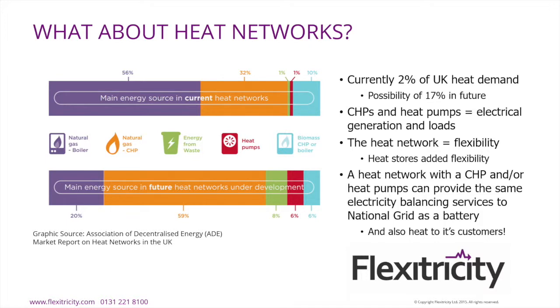Heat networks in particular, rather than just a heat pump or a CHP on its own, are interesting because the network itself is flexible. There's a lot of thermal inertia in the network, and when you add a heat store, you get even more thermal inertia, so you can flex the system without affecting the heat delivered to customers.